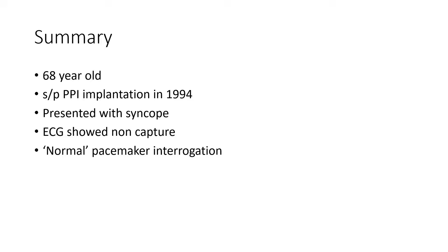So before we proceed further, let's take a moment to define this problem. First, this patient had failure to pace the appropriate chamber. This can either be due to failure of output or failure of capture. As we can see on the ECG, there were pacemaker spikes, but no capture. So this was a case of non-capture. Secondly, this was an intermittent problem. Since taking the ECG and getting shifted to the interrogation room, the patient had somehow reverted back to a normal interrogation. So an intermittent problem may be due to a problem with the electrode endocardial interface.